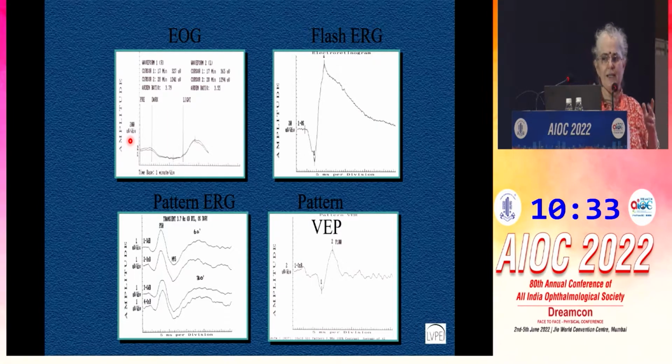Whenever you get any output, first you should make sure that if somebody has written ERG or EOG or VEP, it looks like what it is supposed to look like. If it doesn't look like this, then it is noise. The machine will still give you some output, but it will be noise. It is not the true wave. Okay? And as I said, we look at the...